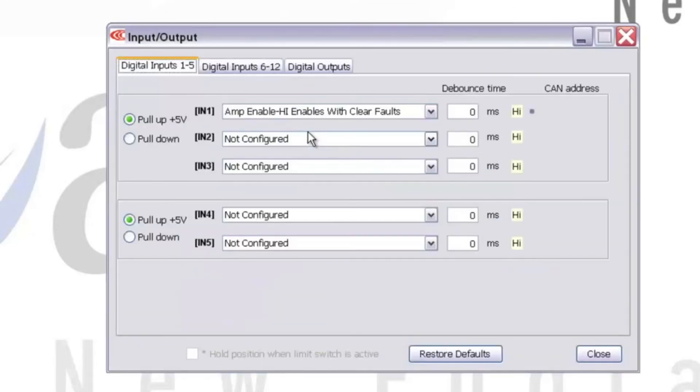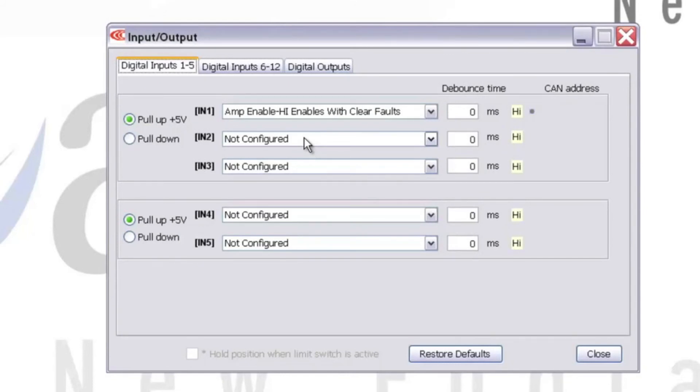We need to click on the Input Output button on the CME2 main screen, which brings up a window displaying our various I/O settings. IN1 is our enable input, so we can select the pull-up plus 5 volts on the left-hand side, then select Amp Enable High, Enables with Clear Fault.